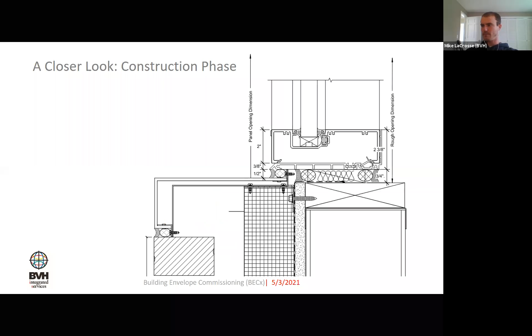Getting back to the next example: fog testing, which I've mentioned a couple times. One way we can check the air barrier itself at transitions for air tightness, such as a wall transitioning to a foundation or a wall transitioning to a curtain wall, which is what we're testing in this example, is with this pretty crude test approach called fog testing, or first instance testing. We're testing the first instance of this wall air barrier to curtain wall rough opening transition to see if it's airtight or not. In this photo, he's taking essentially a shop vac with a fog machine inside it, and he's blowing this fog at the detail.